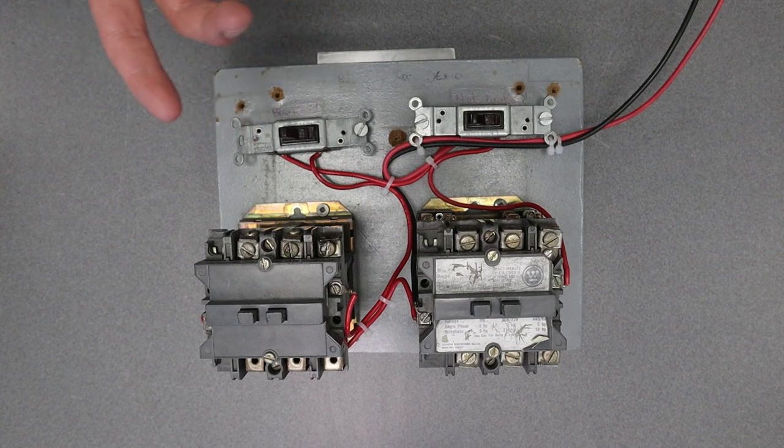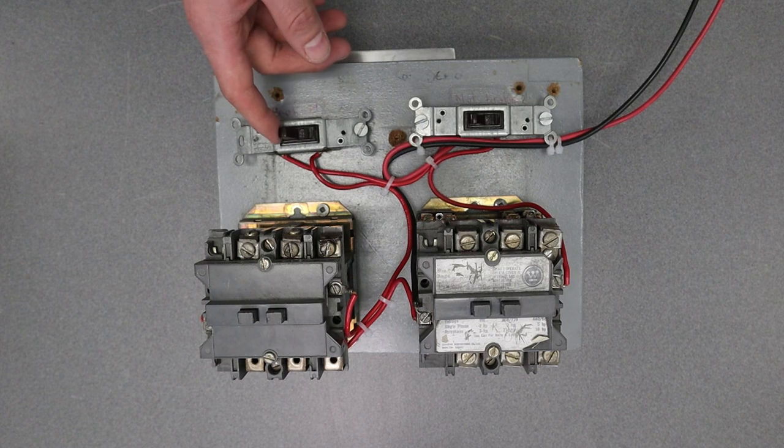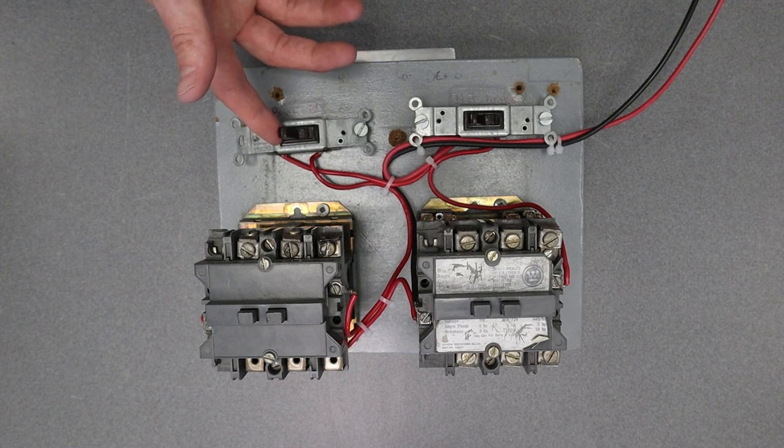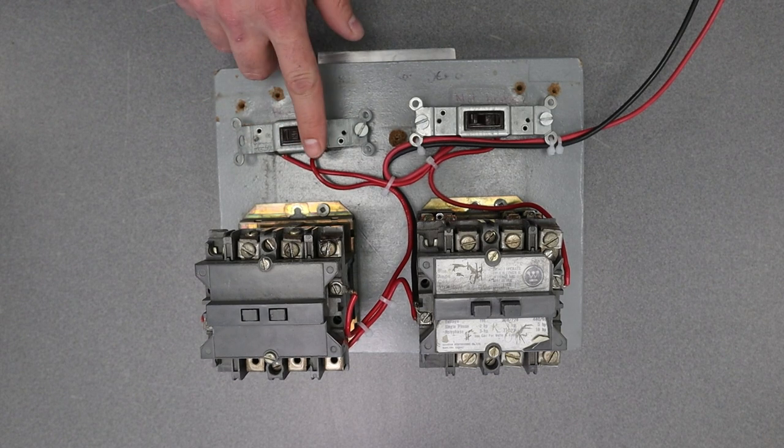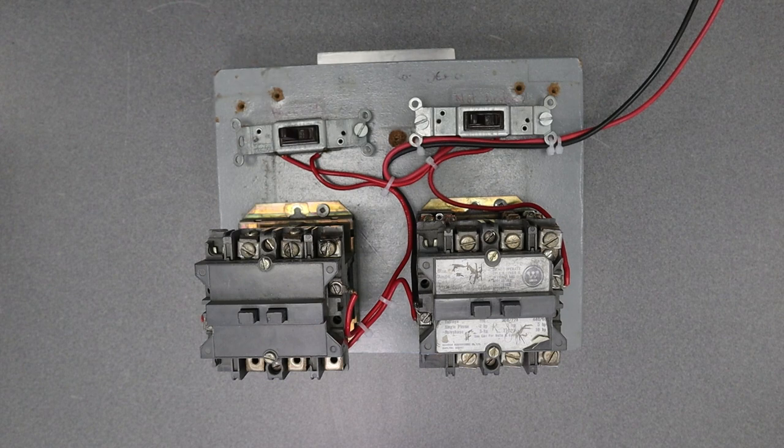The other one here actually has a faulty or a missing shading coil or a broken shading coil. And we'll see what happens when I turn it on. We get that terribly loud sound or that chattering.